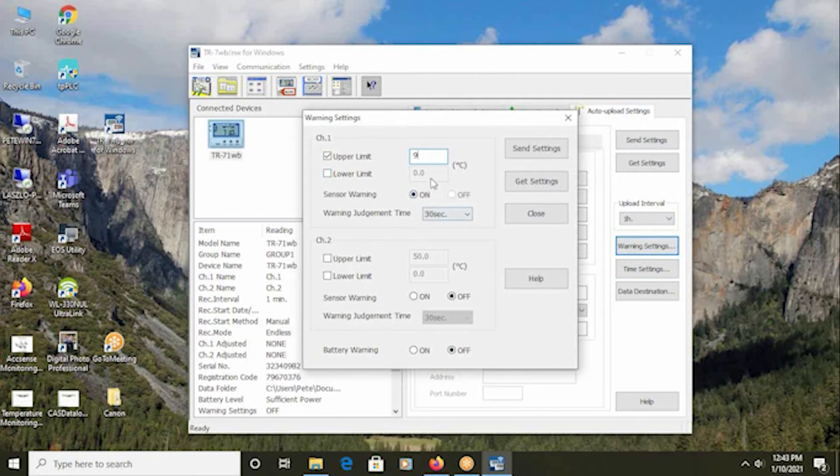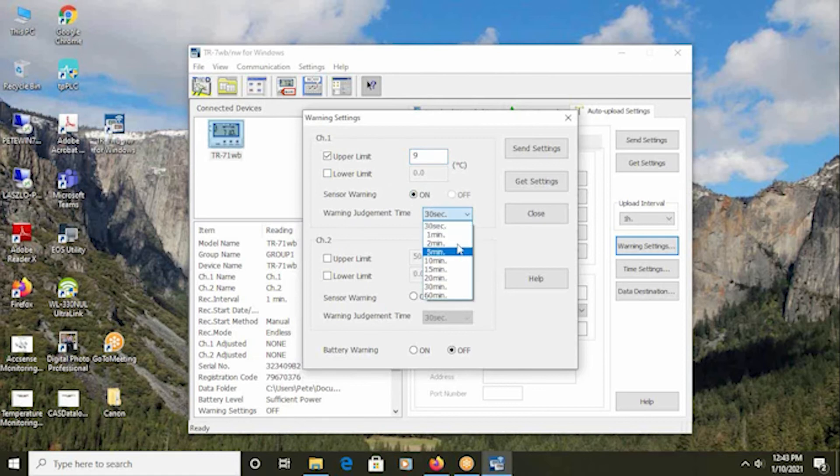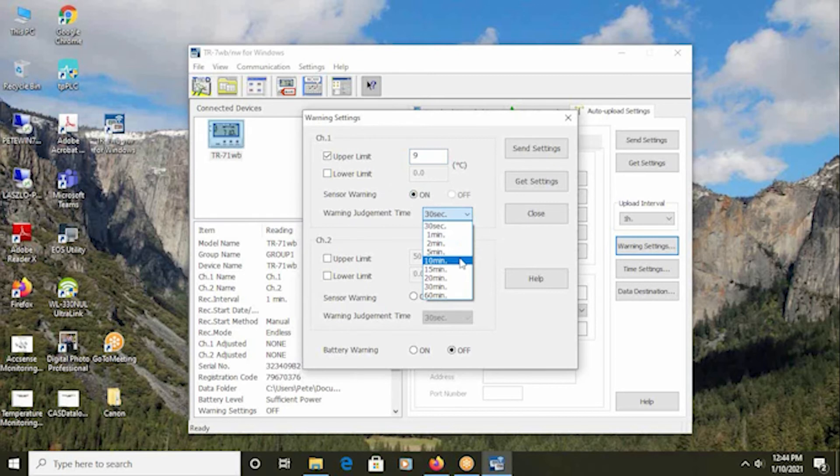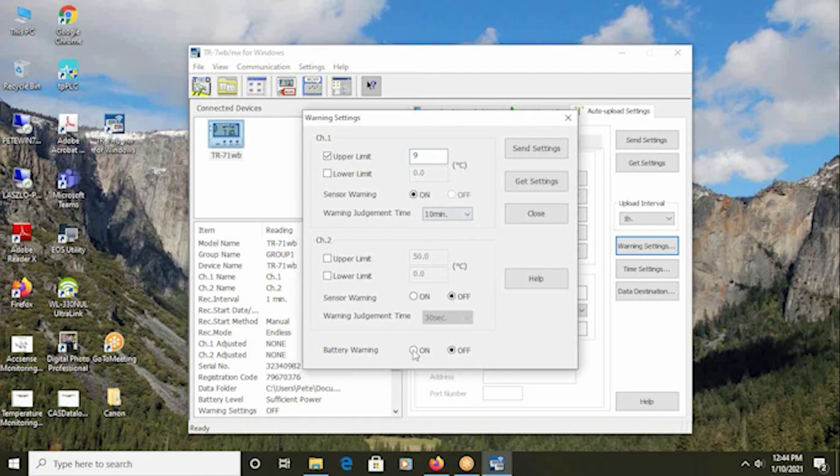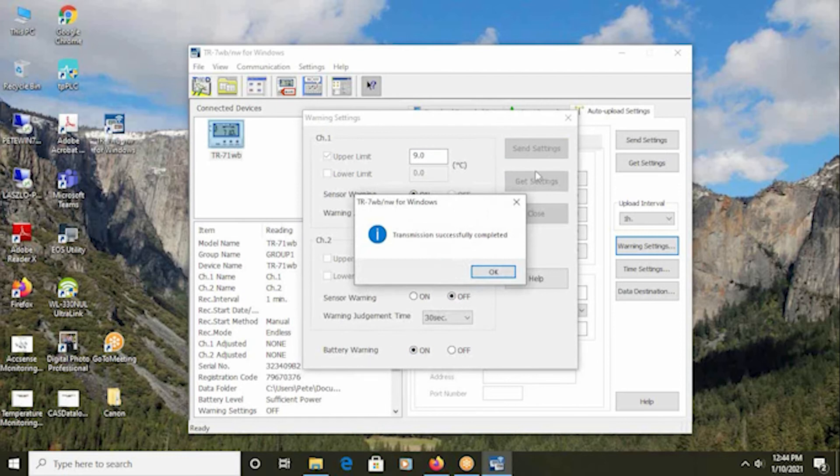I want the sensor warning to be on and the warning judgment time. The warning judgment time is the period that the condition must remain active before an alarm is generated. If a thermal buffer is surrounding the end of the probe, you have an automatic judgment time because of the time constant for the temperature to reach the sensor tip. In addition, you could say during restock or retrieval periods, normally we would have a 10 minute cycle. Whatever fits the application, this choice should be made. If you want to receive battery warning alarms to let you know when the battery level in the logger has reached 20% left, this button should also be turned to on. It's important to remember to send the settings by clicking the Send Settings button to the logger to complete this portion of the setup. Once you've sent the settings, you can close the window.